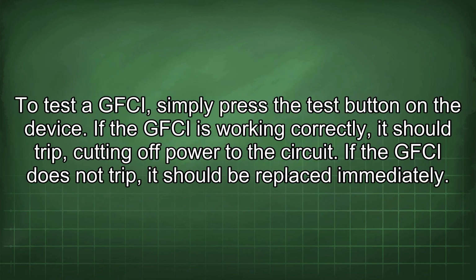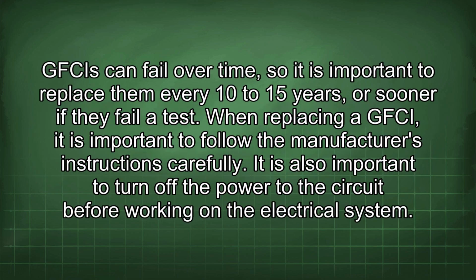To test a GFCI, simply press the test button on the device. If the GFCI is working correctly, it should trip, cutting off power to the circuit. If the GFCI does not trip, it should be replaced immediately. GFCIs can fail over time, so it is important to replace them every 10 to 15 years or sooner if they fail a test. When replacing a GFCI, it is important to follow the manufacturer's instructions carefully. It is also important to turn off the power to the circuit before working on the electrical system.